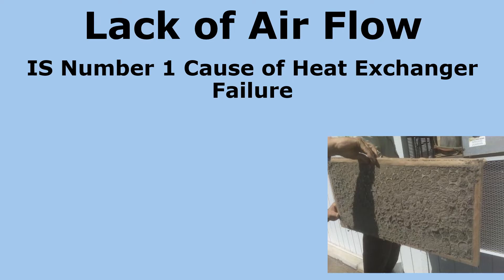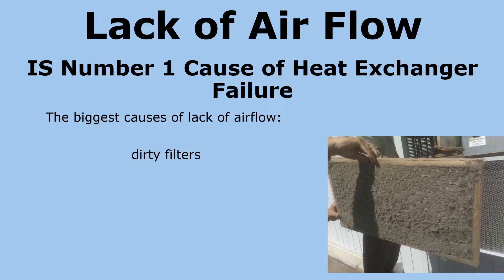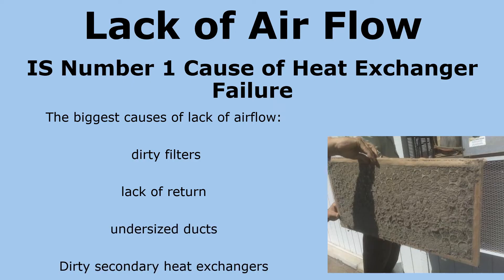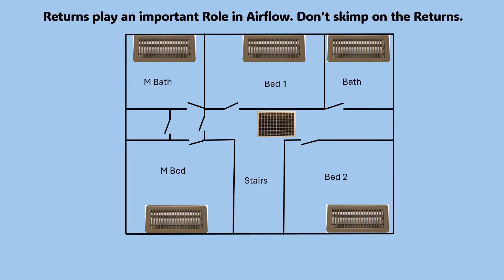Lack of airflow is the number one cause of heat exchanger failure. The biggest causes of lack of airflow are: dirty filters, lack of return, undersized ducts, and dirty secondary heat exchangers. Returns play an important role in airflow — don't skimp on returns. Due to the cost-driven nature of our business, inadequate airflow is a more likely problem and is almost always caused by a lack of return air or undersized ducts.